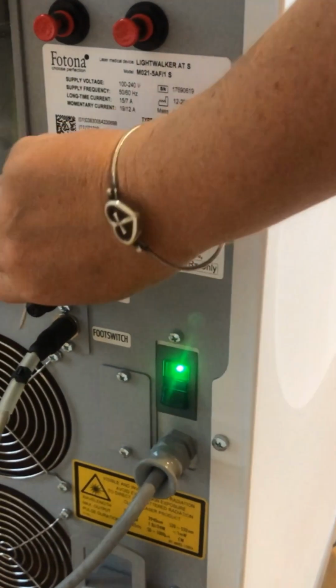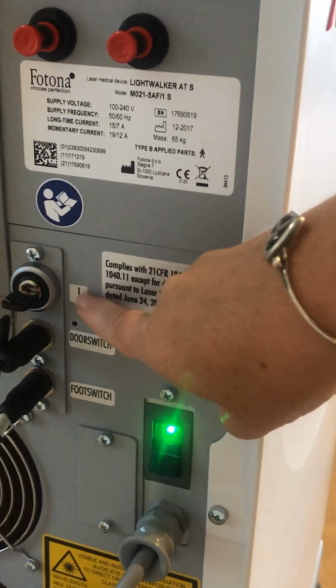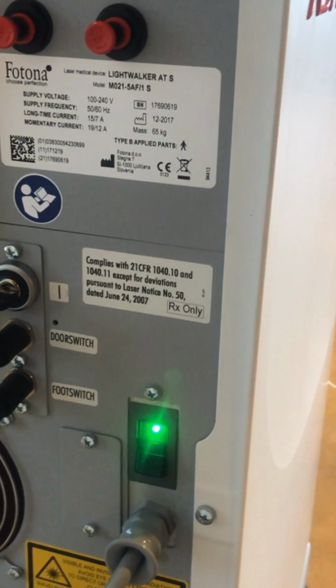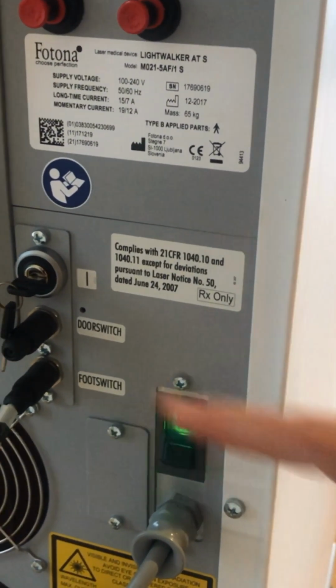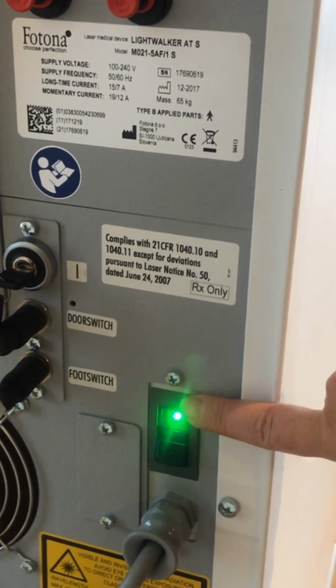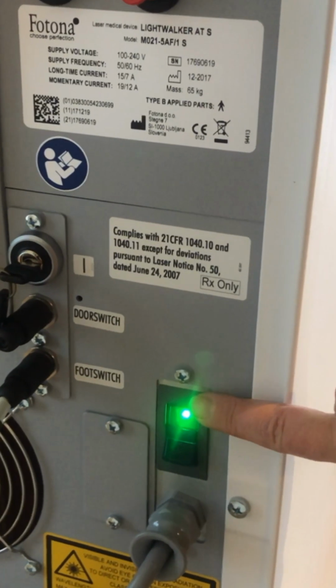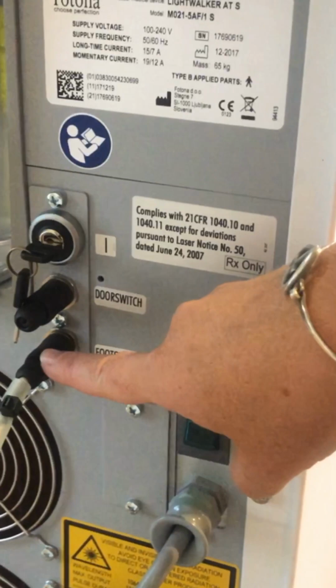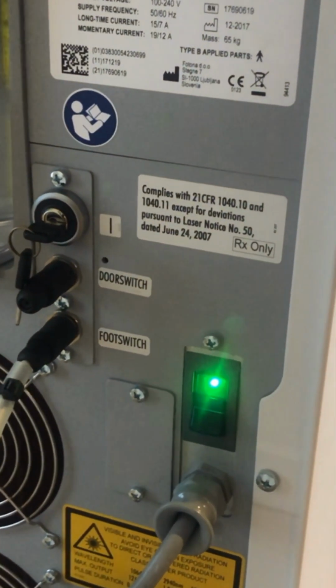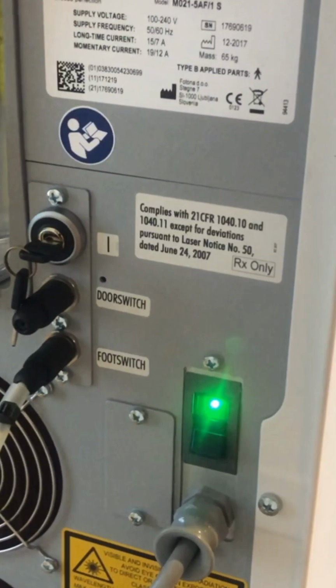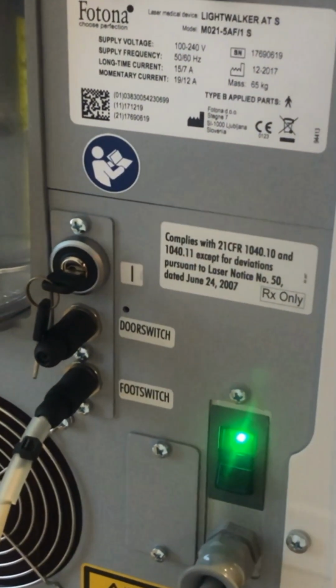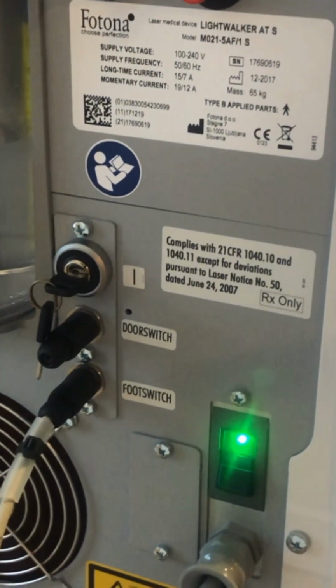This is your key switch that has to be turned perpendicular to the line so that will allow the laser to work. Once those two are in function, the laser will work. Also, the foot pedal must be attached or the machine will not work. If you have the wireless, there's going to be a mechanism back here that would take its place.